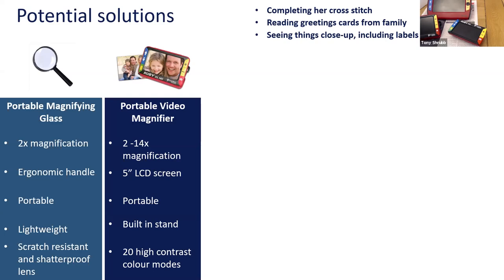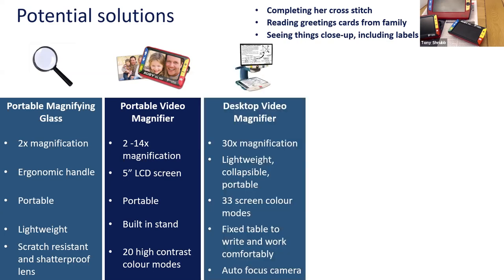Next we have electronic portable video magnifiers. These differ in that you've got continuous magnification from 2 to 14 times, varying depending on screen size. The one featured has a five-inch screen. It's portable, has a built-in reading stand at a 45-degree angle, and — importantly — 20 high-contrast colour modes. Moving on, we have bigger desktop video magnifiers — generally a 24-inch screen with a camera facing down onto an XY table which moves in all directions.